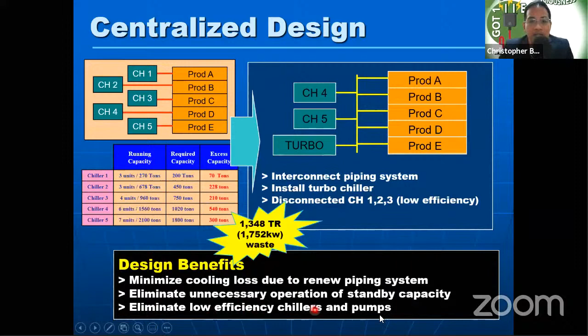So on design benefits, we minimize cooling loss due to renewed piping system. We eliminated unnecessary operation of standby capacity. Before, you needed many standby units because we are into production, manufacturing business, so you need redundancy too. If you have many systems and many redundancies, more is wasted. Unlike when you centralize, your redundancy gets custom-fit to the centralized piping system. And of course, we eliminate low efficiency chillers and pumps, the old ones.